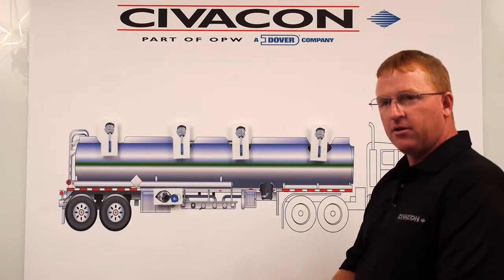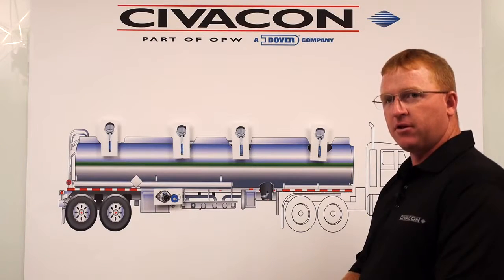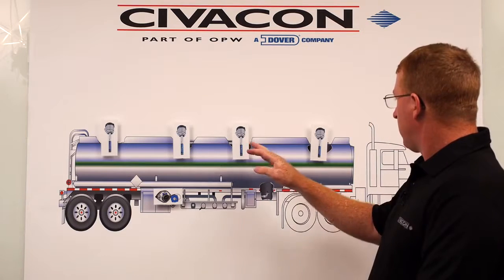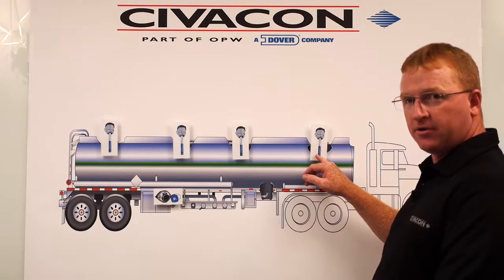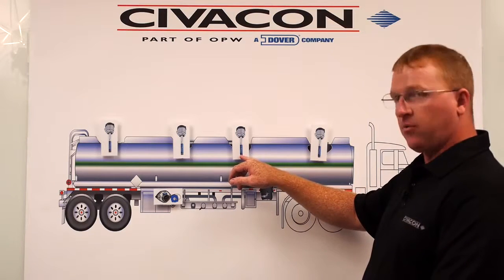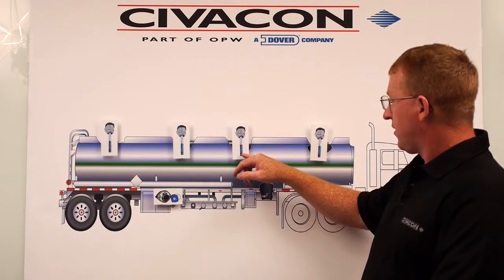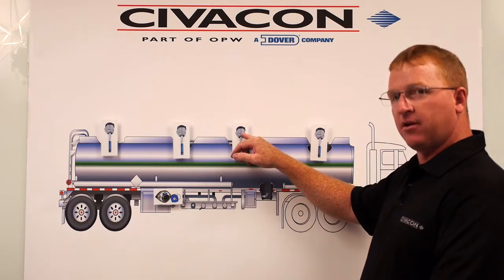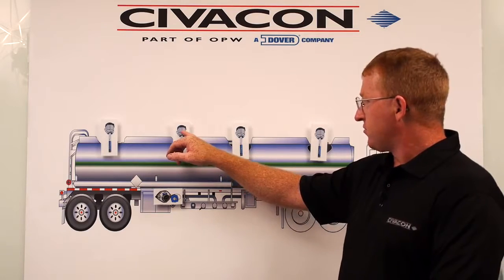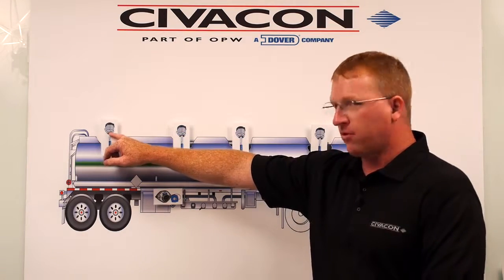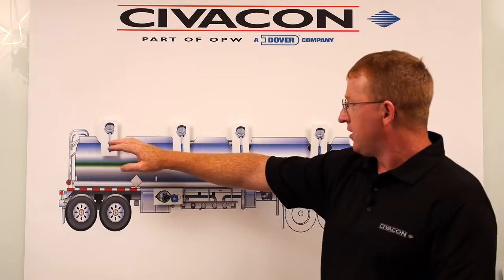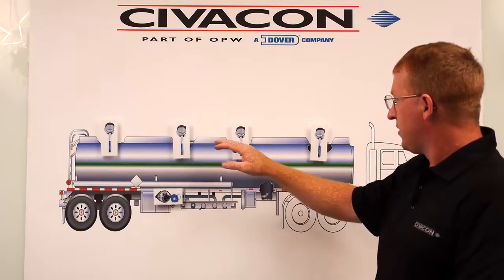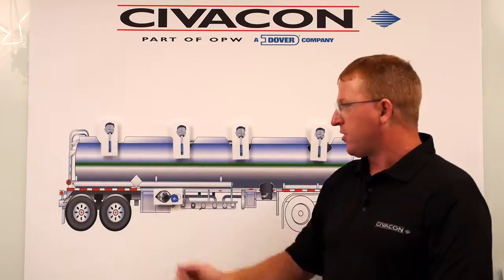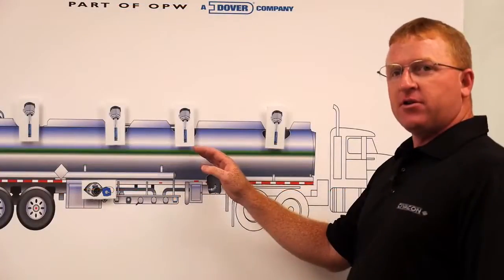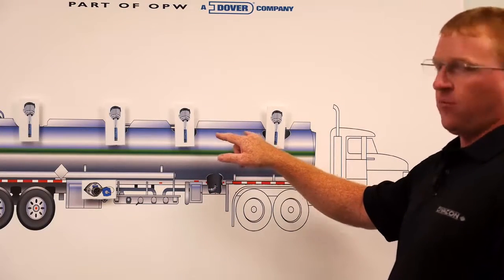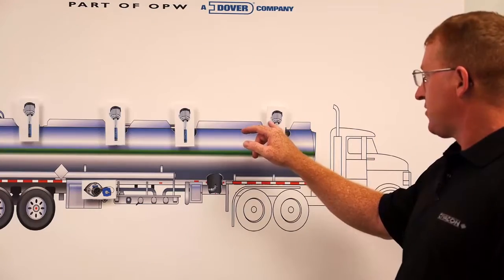Okay, with our truck tester hooked up, it's showing us that number 2 sensor is potentially the issue with our system. That's telling us that number 1 probe is fine. The issue could either be with a wet sensor or a wiring issue, and the wiring issue doesn't exactly have to be in this number 2 housing. Remember, the wiring starts at the rear, goes in number 4 in this display that has 4 compartments. It'll come in number 4, connect to number 3, and then to number 2. So any one of these points could potentially be the wiring issue. A less likely culprit would be the wiring between number 1 and 2 probes, which in that case would have to be the orange wire.